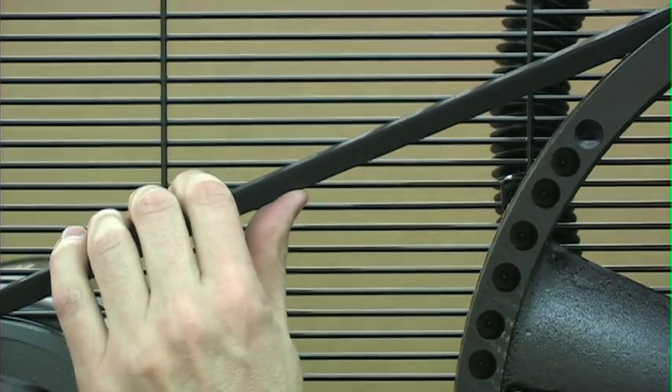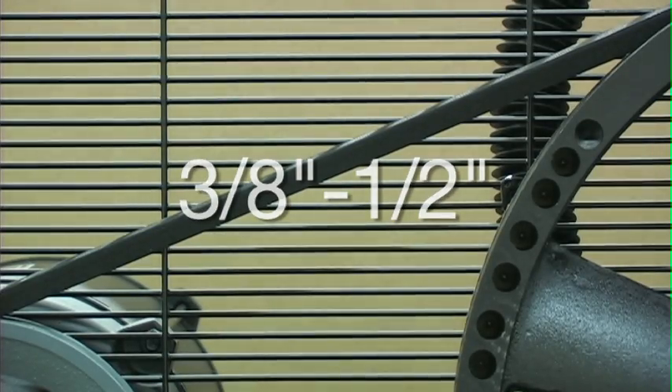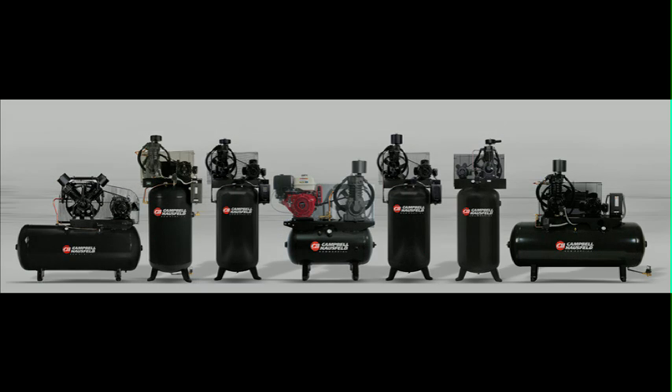Every three months, check the belt tension and adjust to allow 3/8 to 1/2 inch deflection with normal thumb pressure. We hope this video was helpful to maintain your new Campbell Hausfeld two-stage air compressor. If you have any questions, please contact Campbell Hausfeld Customer Service.